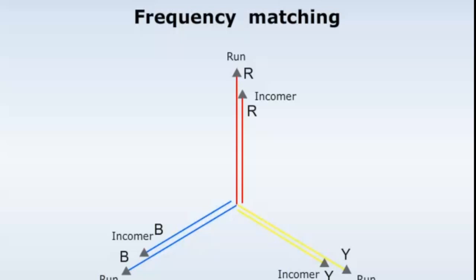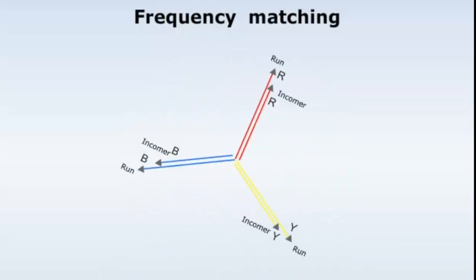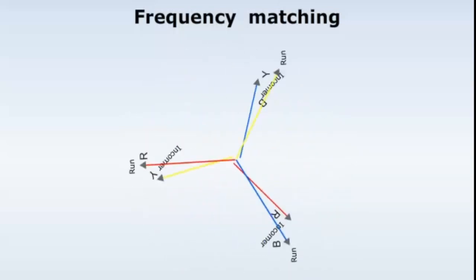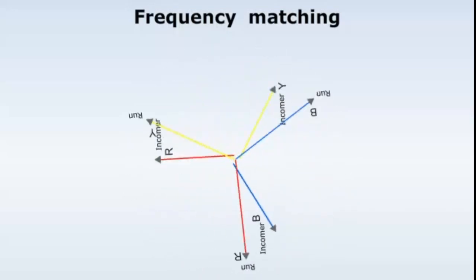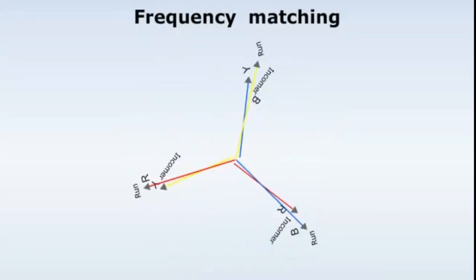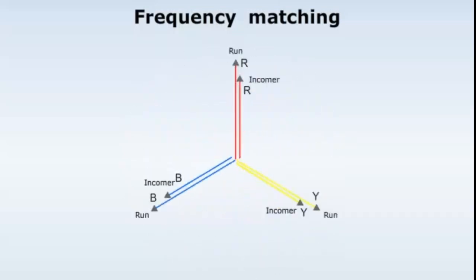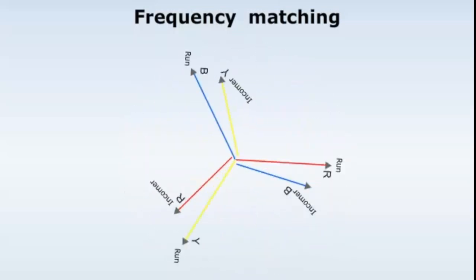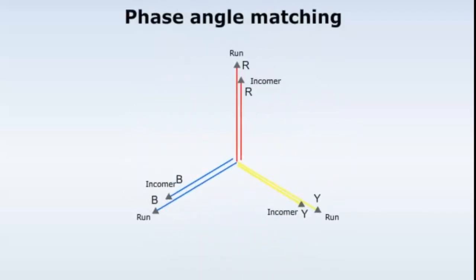The third condition is that the frequency of the incoming alternator should match the frequency of the running alternator. The frequencies will be equal when the alternators are rotating at the same speed. A difference in frequency indicates that the stored energy in the rotor of the incoming alternator is either greater or less than the running alternator. Therefore, if paralleling is carried out when a frequency difference exists, a surge will take place.